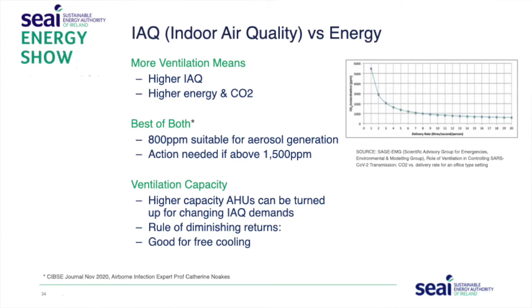Now, the rates that were recommended, and Michael went into this in great detail, flipped around during the middle of COVID, but it's more pragmatically come back towards, I would say, 800 ppm is a very healthy design target. I'm quoting here Professor Noakes, published in the CIBSE Journal in November 2020. As an airborne infection expert, she said that 800 is fine, is good for airborne aerosols, and that you can range it up a bit, but once you go over 1500, you need to be doing something about it. So if we target 800, we're really in good shape, and that would tie in with Michael's 10 litres per second.